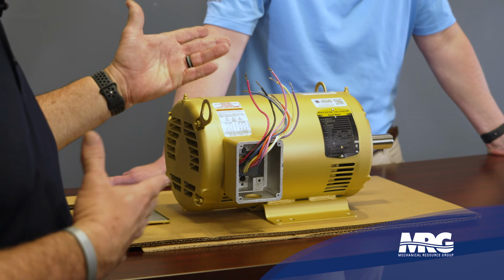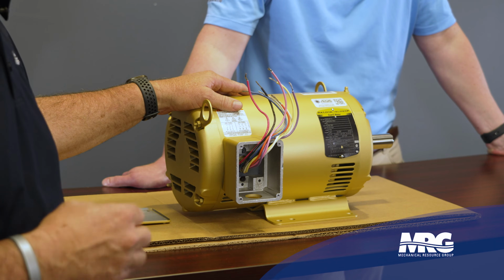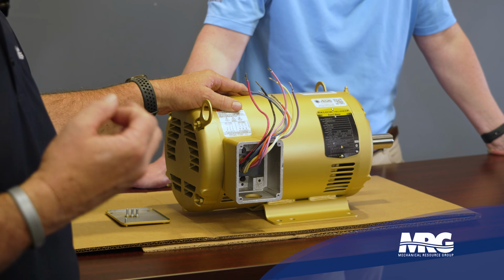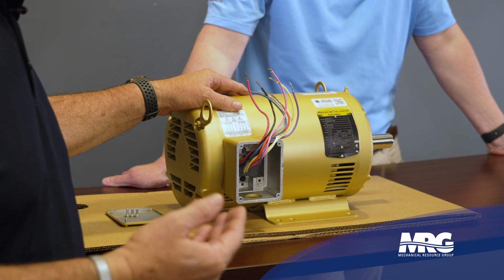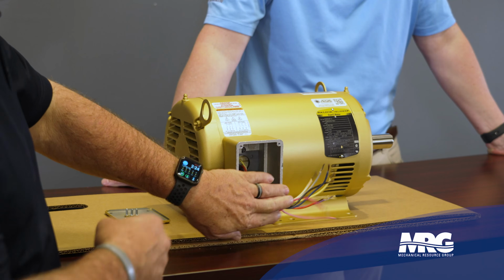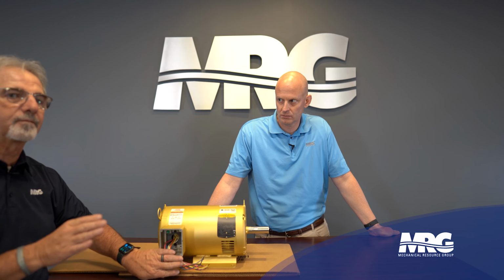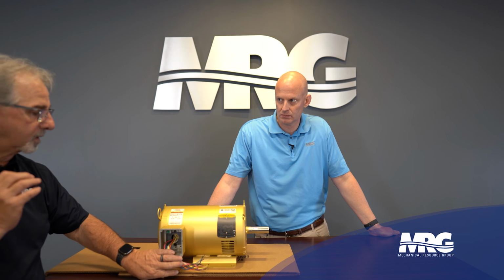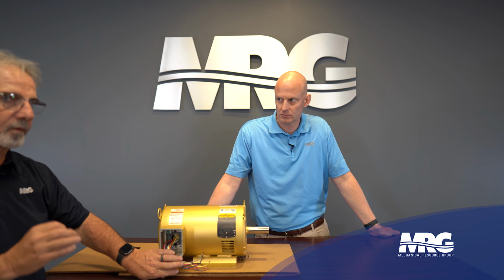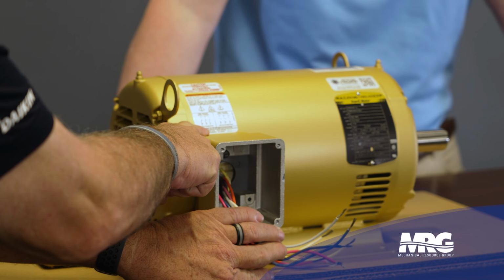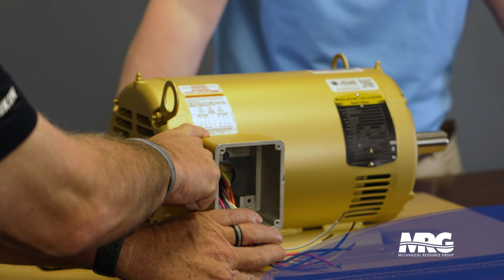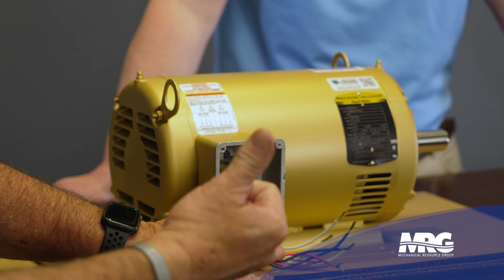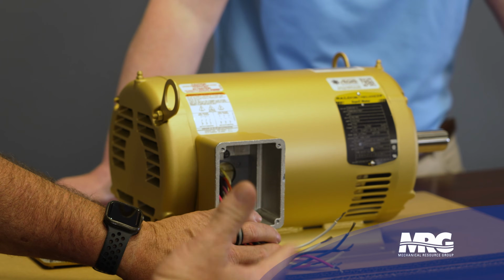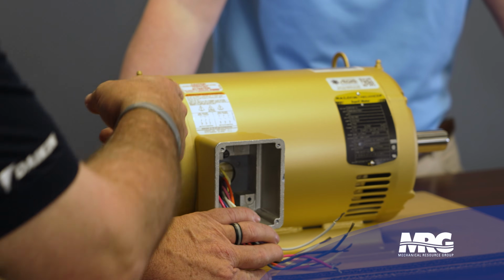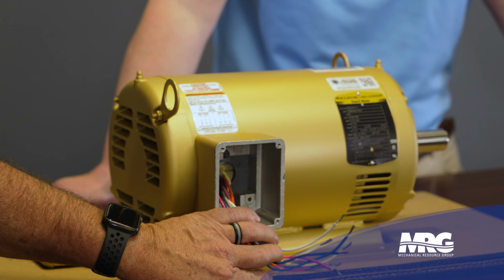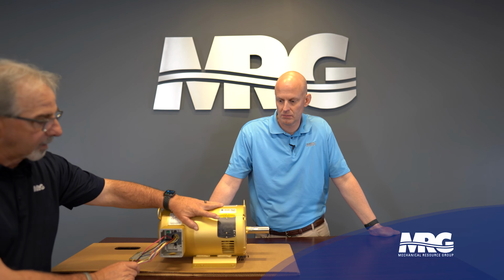Absolutely. So when you first walk up to the motor, there's some information that you need to gather, and you need to know what your starting method is. If your starting method is an across-the-line starter, then you're going to hook this motor up a certain way. And if you'll notice on the top, now not all motors have this, so that's why you need to know the numbering system and how to connect for what voltage you're at. But on this particular motor, Baldor puts a sticker on here, and this sticker will give you both low and high. Low voltage is always considered 208, 230. High voltage is always considered 480. So it tells you how to connect the motor and tells you which motors are line and load. The other thing that you want to take a look at is the nameplate.